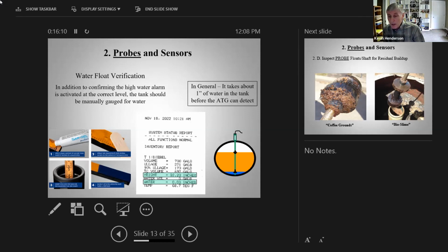You need to look at your specifications, of course, on your probe to see what is the minimum level of water that probe is capable of detecting. And with a typical Veeder probe, it's like 0.9 inches. So we just say 1 inch. You have to have 1 inch of water in the tank before that probe will even register any water in the tank. So that's why a lot of times you'll see 0.00 inches on the Veeder report. But if you went out and did a manual sticking of the tank, you might see, well, it's got a ½ inch in it or whatever. So the tank gauge just can't see anything that small. So you just need to be aware of that. I personally do not like relying on the tank gauge to tell me if there's water in the tank or not. I still want to periodically manually stick that tank.